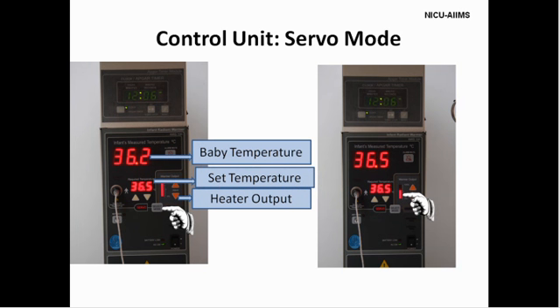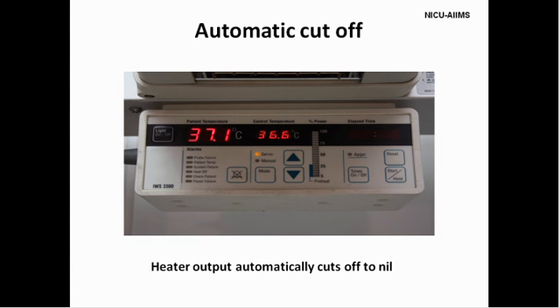We have to set a particular temperature in the servo mode. Usually this is between 36.5 and 37.5 degrees Celsius. The control unit displays both the set temperature and the baby's temperature, and the heater output automatically is adjusted up and down based on the difference between the two temperatures. This heater output can be displayed in the form of a digital display or an analog display. Now let us see the control panel of this unit.